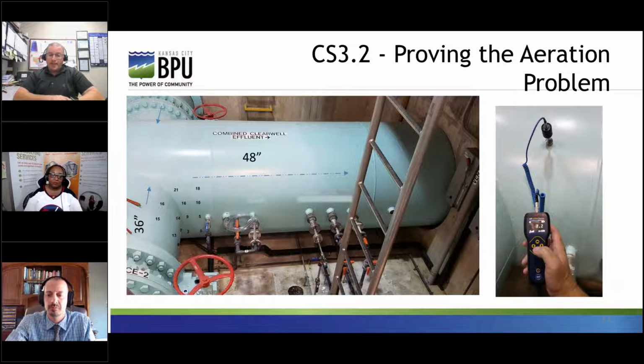Well, ultrasound is a fantastic tool for finding friction, impacting, and turbulence. And in this case, it was the air bubbles combining and breaking apart that was easy to hear and caused increased decibel readings. Put the magnetic probe on the pipe, record its reading in decibels, and mark it on the pipe with a dry erase marker. Those points in the photo on the left represent the dB readings the Ultra Checker observed.